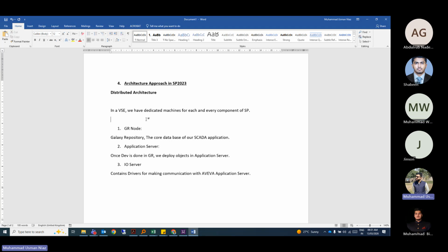If we talk about the master SCADA, the one that you will see in the RIA farms, it is a very high-end SCADA. So to minimize the downtime, to distribute the resources, the application, working and development, it is very mandatory and advisable from Aveva that we make separate nodes, separate VMs for all of these machines. We can even have separate hardware, but from the budget perspective it is advisable that we do the virtualization.